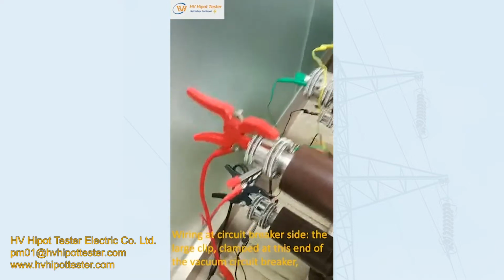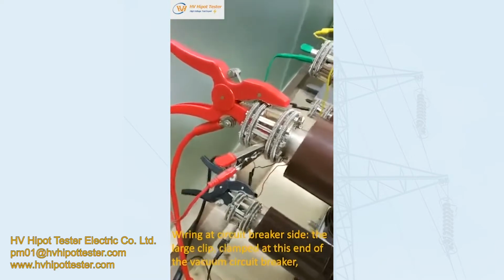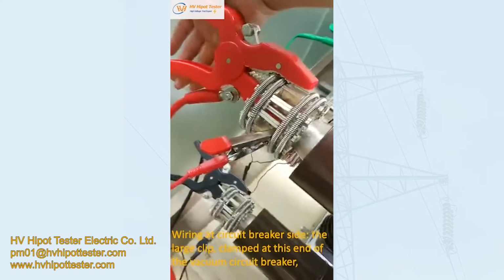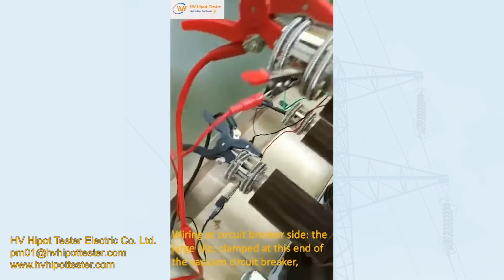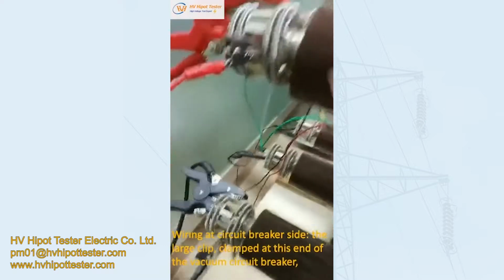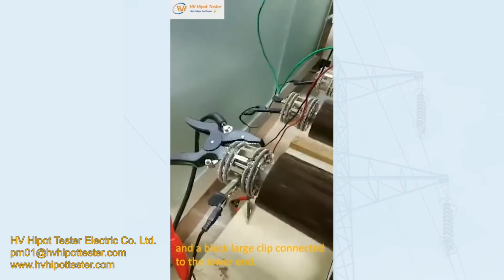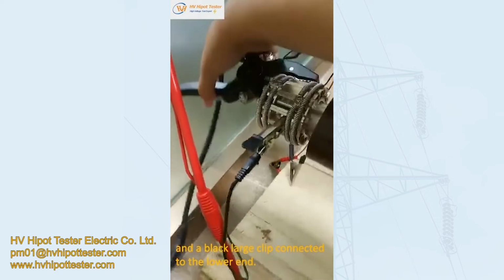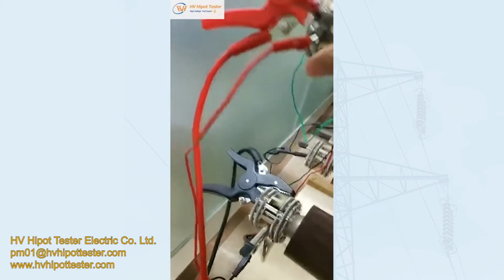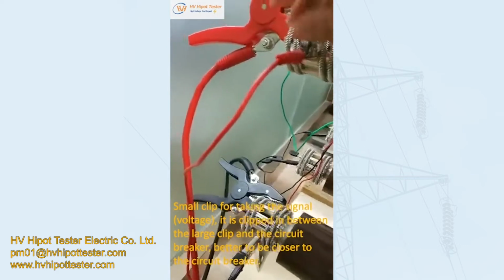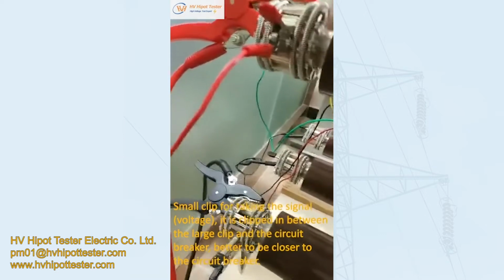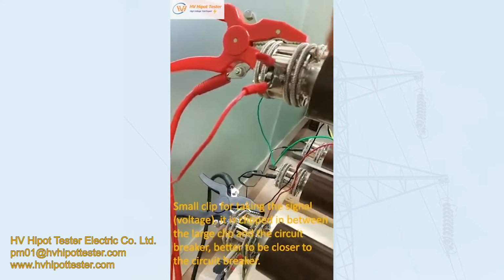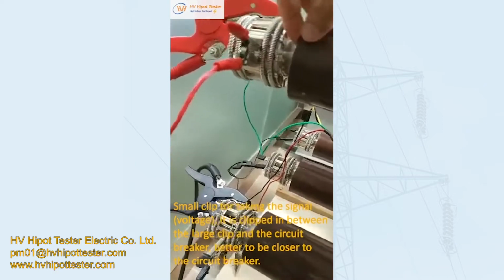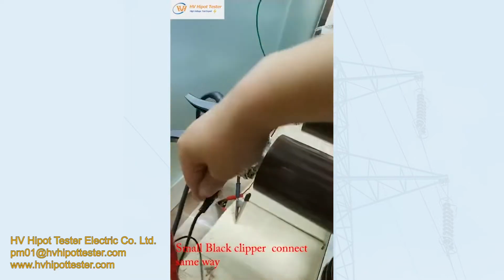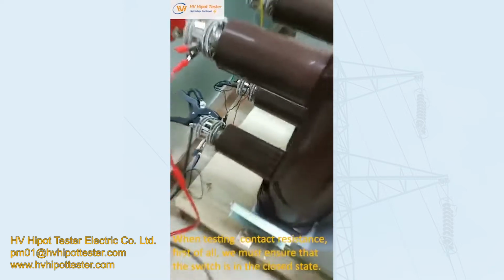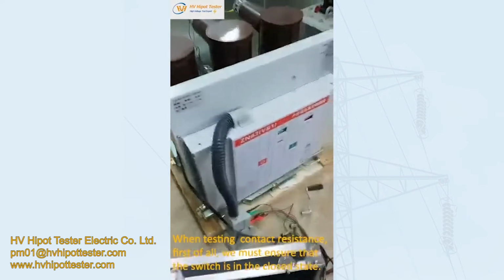Wiring at the circuit breaker side: the large clip is clamped at the end of the vacuum circuit breaker, and the black large clip is connected to the lower end. The small clip is for taking the signal voltage, clipped between the large clip and the circuit breaker, better placed closer to the circuit breaker. The small black clip collects the same way.